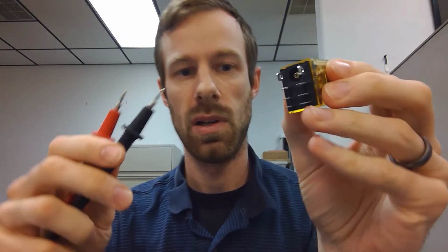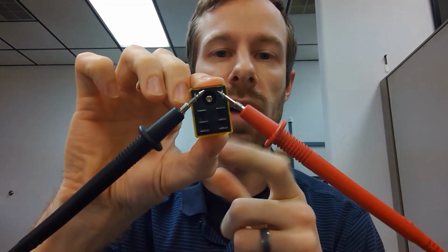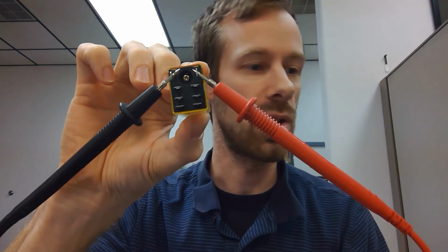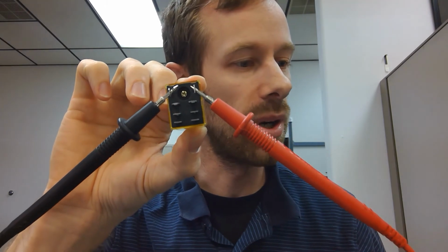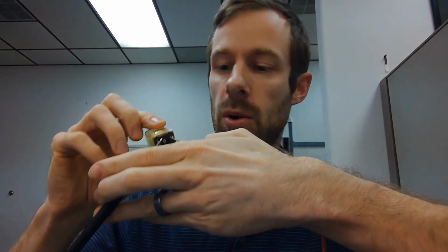Now, a good, easy way to test these relays, if you have a multimeter around, is just change it over to the resistance setting. So this one I've changed it down. I'll start with the 2 kilo ohm range just to see. Might have to turn that one down a little bit. And I'm going to connect the 2 leads on this one to these 2 terminals. Usually the 2 that are off by themselves are the coil terminals. And I see 0.649 kilo ohms. So that's about 650 ohms of resistance for that coil.